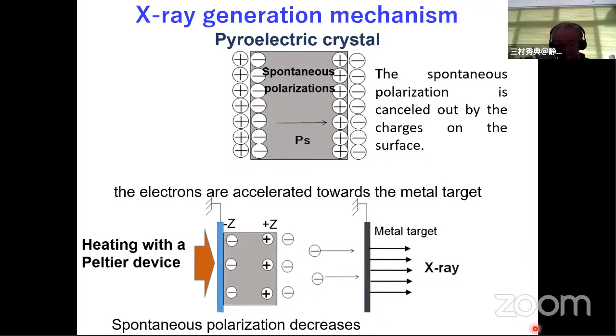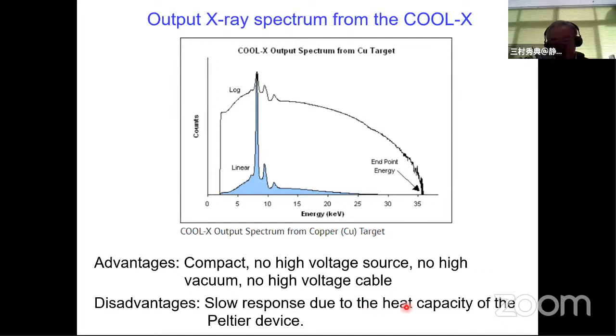This is the output X-ray spectrum obtained with the Cool-X. X-rays up to 35 kilovolts are obtained without any high voltage source. The advantage of the Cool-X is that it is compact. No need for a high voltage source. No need for a high vacuum. No need for a high voltage cable. However, the disadvantage is the slow response due to the heat capacity of the Peltier device.